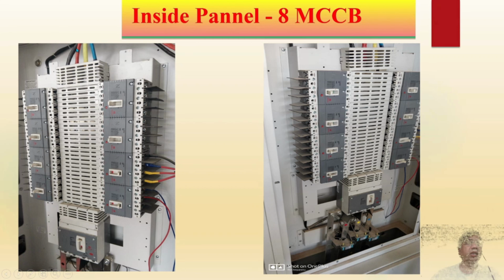These wires were connected here because they faced a challenge fitting this 100 mm wire inside the pocket of the MCCBs. They said it wasn't going in - they needed some adapter, spider link, or lug. Even a normal lug wouldn't go in, since it has a certain size. So there was a big challenge. I'll show you in the next slide. This is how the panel looks from inside. Let's move to the next slide.